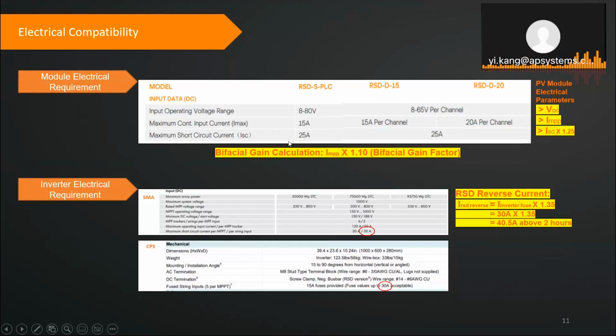The RSD value is 25 amp. So you can calculate from your panel data sheet their RSD value times 1.25 with the safety factor. For the bifacial, not too much favor on the residential market side, but what we learned from the commercial jobs is that most bifacial panels in the field never really gain an additional 10% power, normally below 8%. That's why when we do the calculation, we just use 10% as the bifacial gain factor in reality.